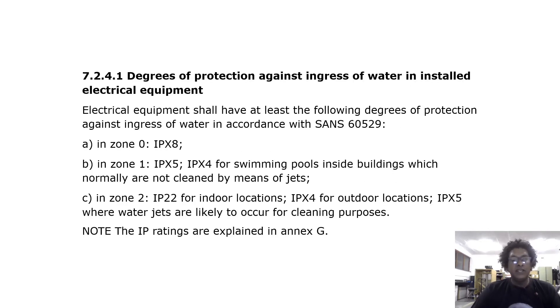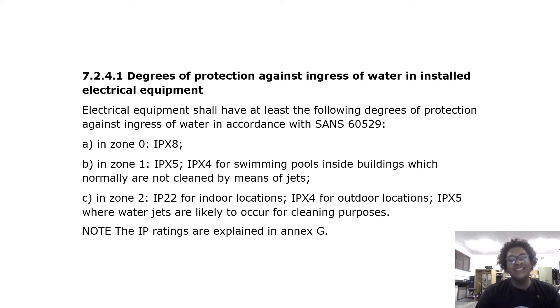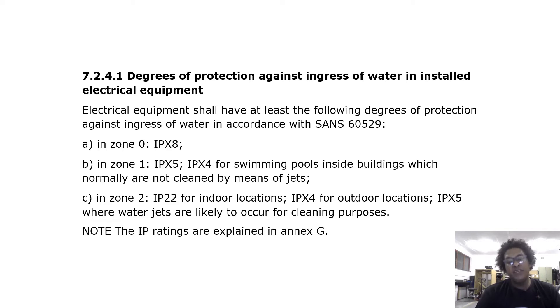For selection and erection of electrical equipment — degrees of protection against ingress of water: installed electrical equipment shall have at least the following degrees of protection in accordance with SANS 60529. In zone 0: IPX8. In zone 1: IPX5, or IPX4 for swimming pools inside buildings not cleaned by means of jets. In zone 2: IP22 for indoor locations; IPX4 for outdoor locations; IPX5 where water jets are likely to occur for cleaning purposes.